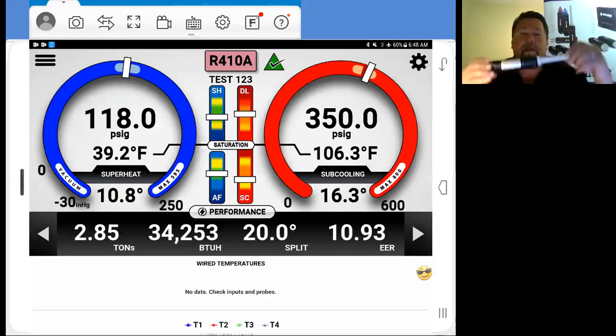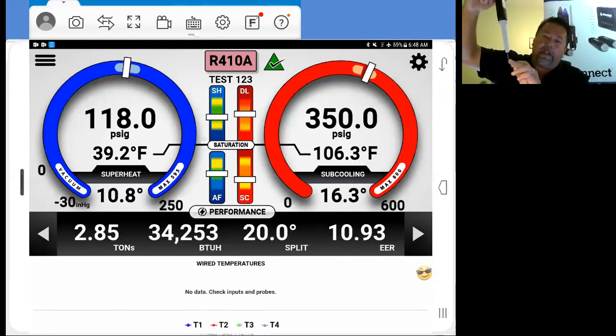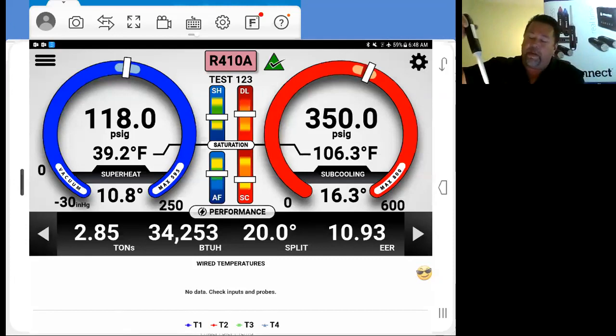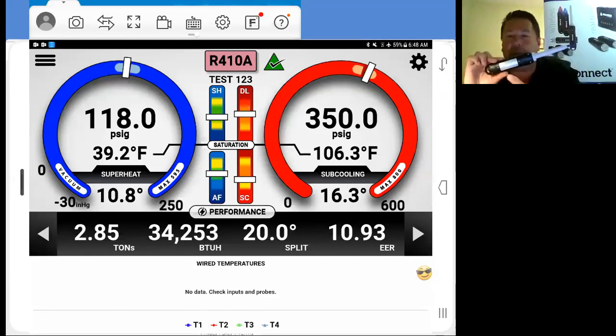A lot of times, what will happen is these probes get put up high and they get dropped, and then suddenly the system's not working. All of a sudden, it's not giving you a temperature, or it's giving you some wacky temperature. We'll show you how to pull this apart real quick. What normally will happen is if this falls on the tip, it'll dislodge the daughter board from the motherboard that's actually in the probe. So just remember, as we showed a few minutes ago, the back where the battery cover is the same side that the sensor is on, because we're going to need to know that to put this back together.